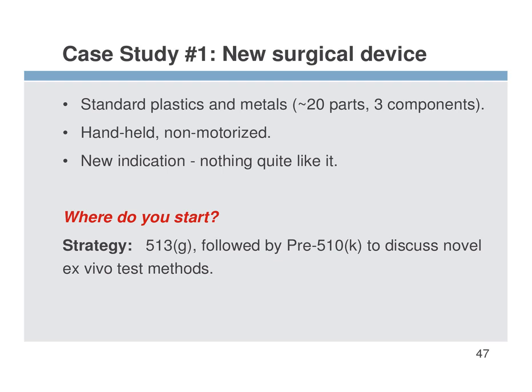And then regardless of what that feedback is, we then submitted a pre-510K because we knew, based on the new indication, there'd be some novel ex vivo test methods. And once again, we had 3 or 4 questions. They answered the 3 or 4 questions and then gave us another dozen more, which we sincerely appreciated. Because after all, it's better to get it early in the process rather than when you sent in your 510K.